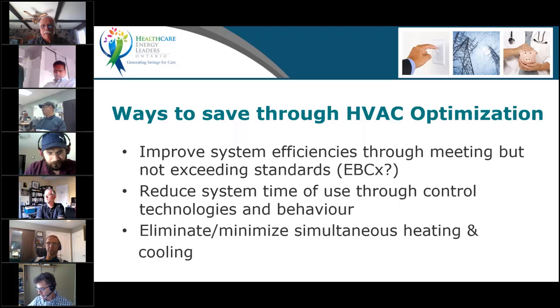Most places will not have budgets to replace the entire system, so you can try to tweak what you have through controls, EBCX, as it says on the first bullet point here. But you can go further than that and try to implement variable speed drives with some VAV boxes if you have them, and I'll talk about that in a case study that I've worked on. It obviously involves some behavior, because occupants may have an impact on some of the terminal units in the system. And there are things you try to eliminate, such as simultaneous heating and cooling, which is really a recommissioning measure.